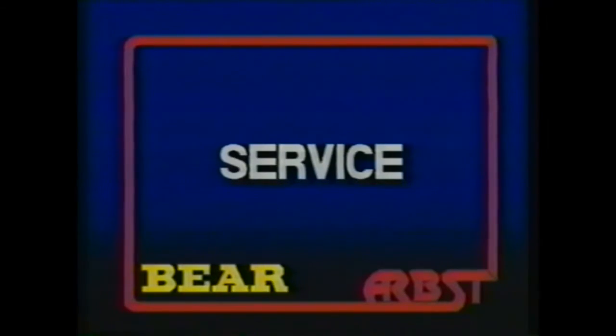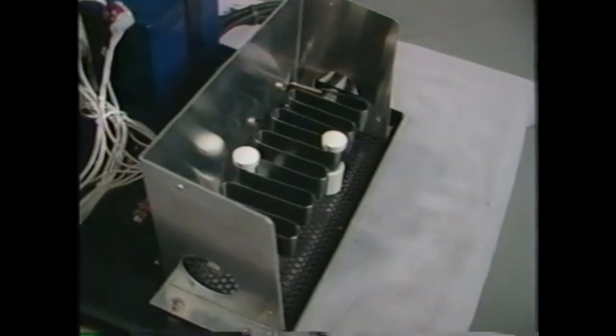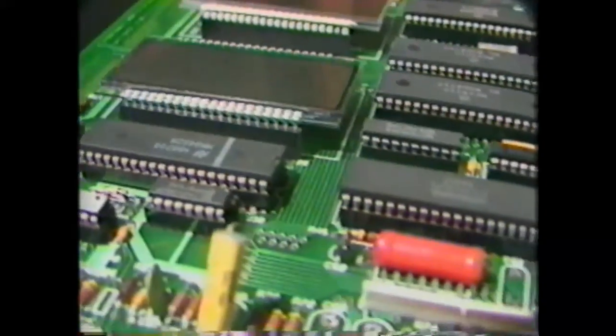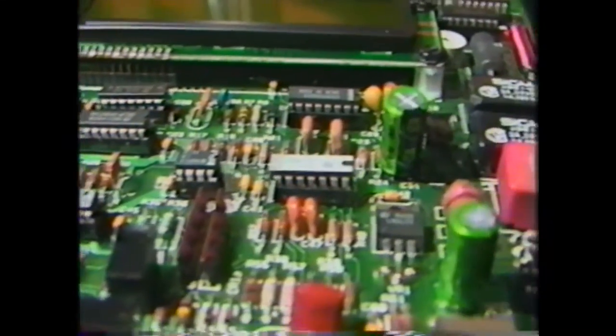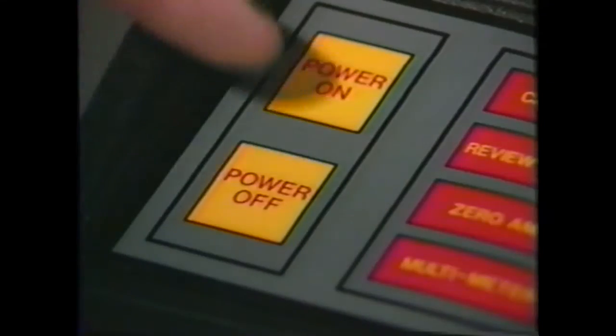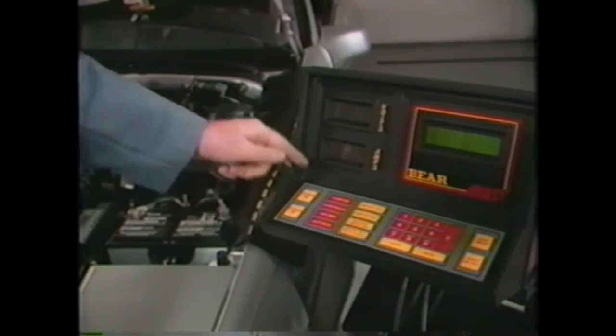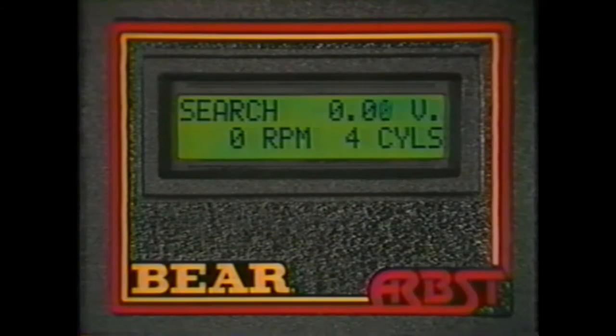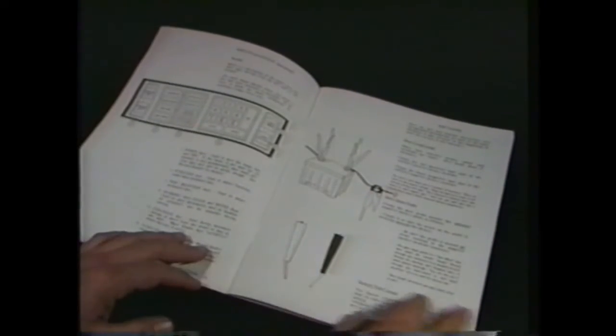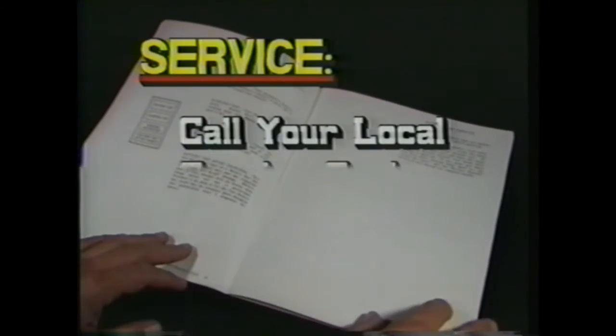Your Bear ARBST tester has been designed with quality components to ensure long, trouble-free service. Should you encounter any operational problem, the following procedure will determine if the problem is field repairable by you or if you need factory service. First, power the unit off, then back on. If the problem still exists, continue with the next step. If nothing appears on the displays when the power on button is pressed, refer to the charger check and internal battery check sections of the operator's manual. If the tester powers up properly but does not read voltage or current, refer to the test leads check section of the operator's manual.